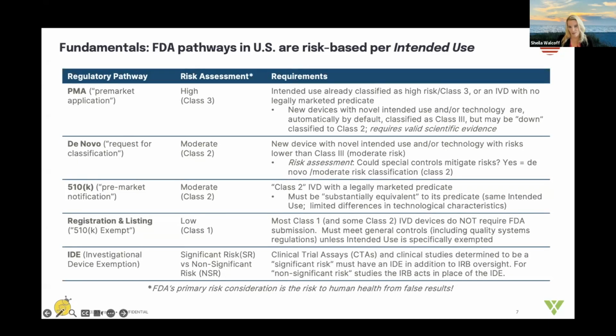Probably the pathway that people are most familiar with is called the 510K. That's a pre-market notification. And in order to use the 510K pathway, you have to find what's called a predicate device, and you have to make a determination that your test system is substantially equivalent to that predicate device. And substantially equivalent doesn't mean exactly the same. The intended use needs to be the same, but you can have technological differences so long as those do not introduce new risks of safety and effectiveness. And sometimes there's a discussion with the agency about that.